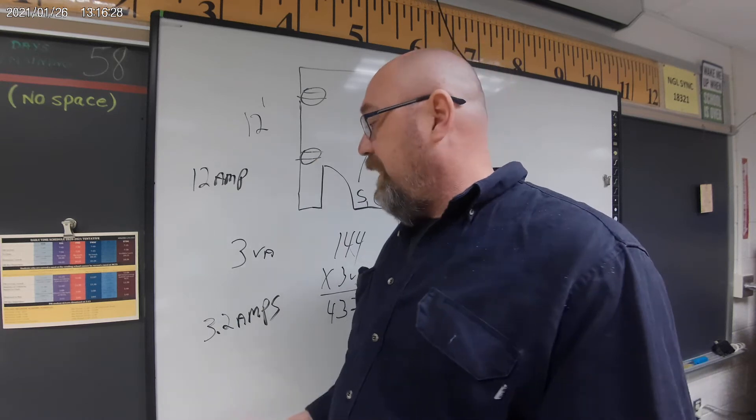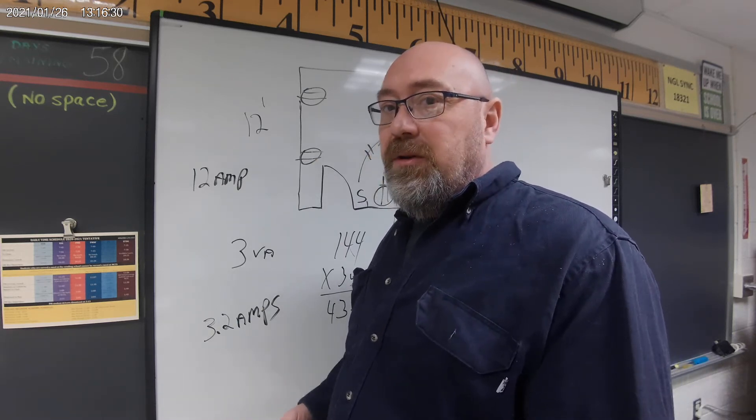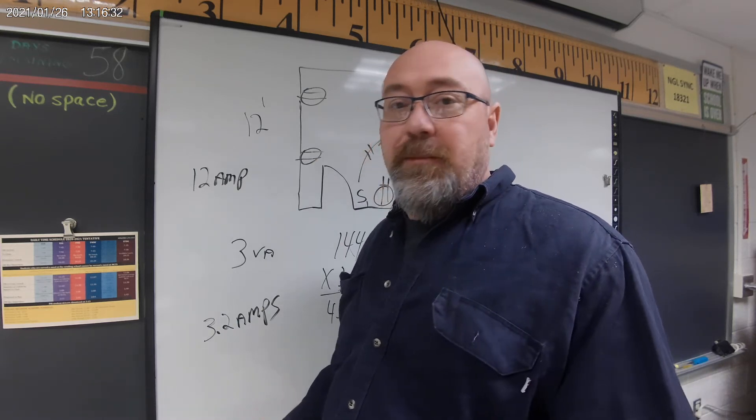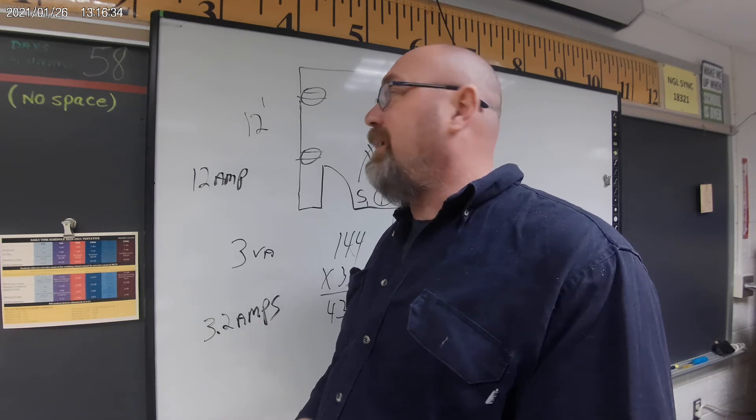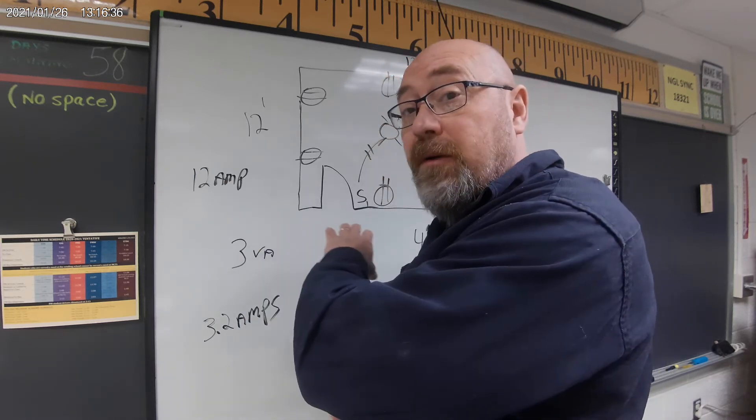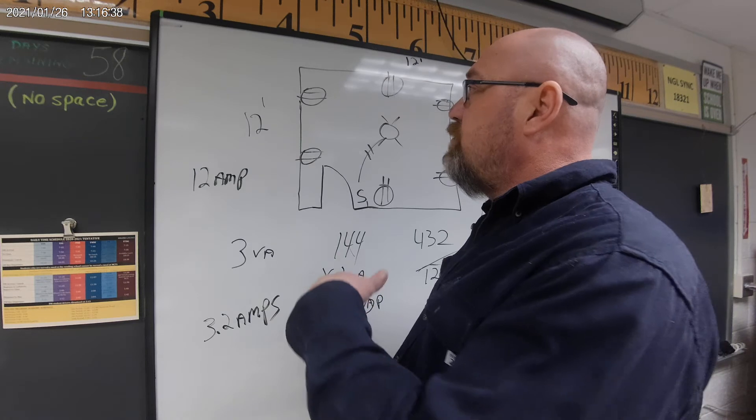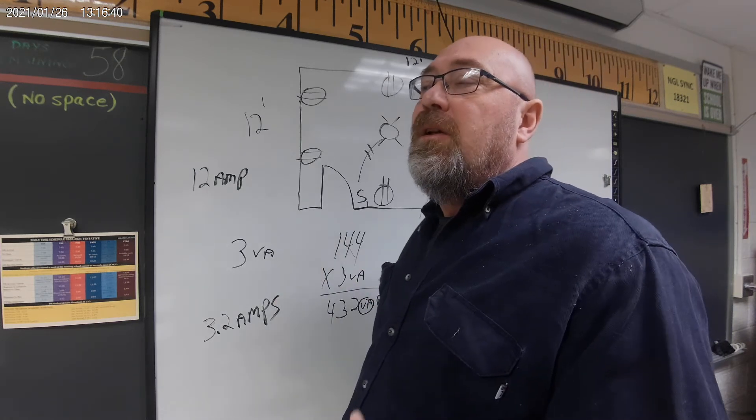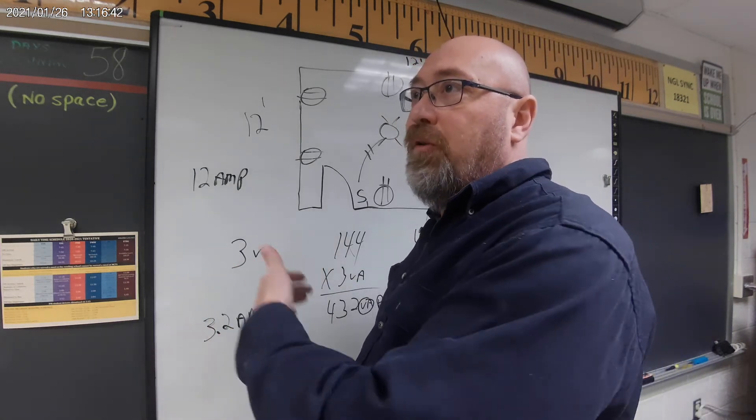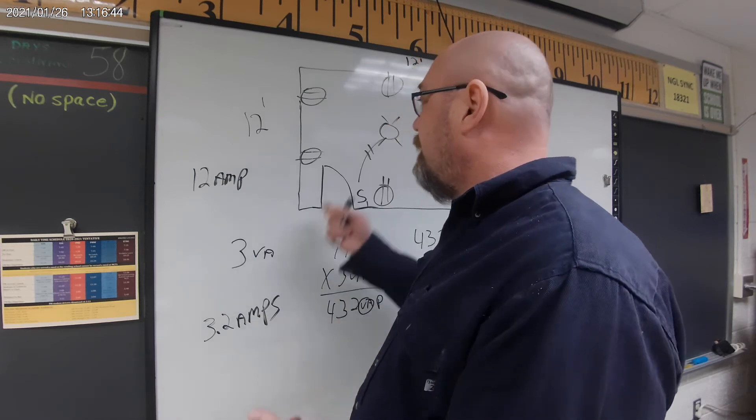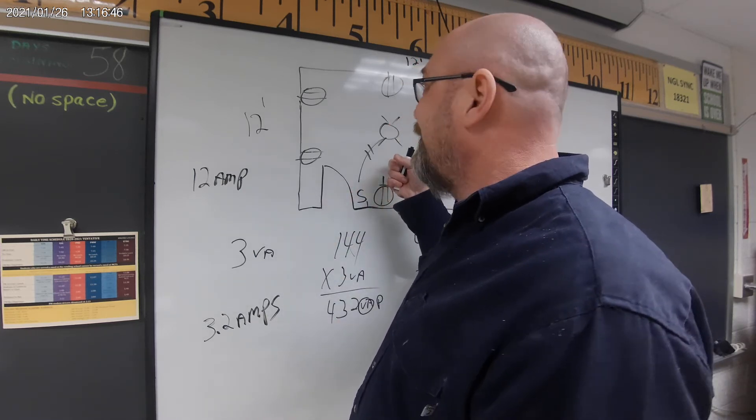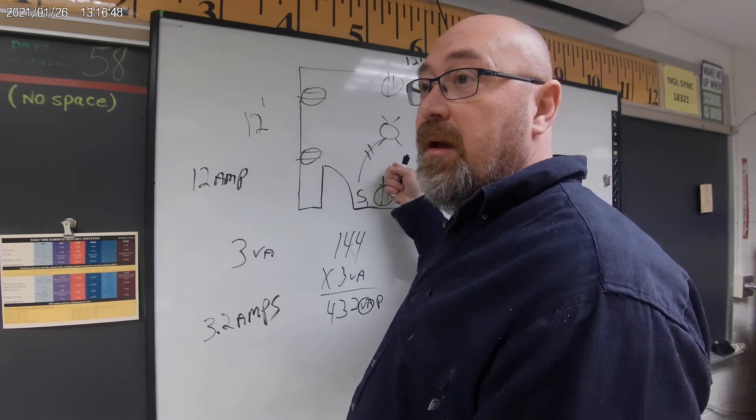If I had two 12 by 12 bedrooms, I could easily put those both on the same circuit because we're drawing less than seven amps for those two bedrooms. The preferred method is no more than eight devices on a circuit. If I have these bedrooms and they're exactly the same, I have 16 devices on a circuit.